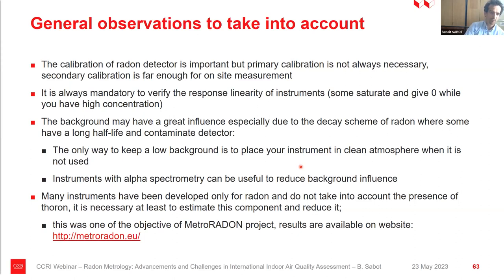But it is very important to check the linearity of instruments, because for some, you may get just a value of zero because they are totally saturated by high activity concentration. It is important to take into account the background of the detector. And often one of the problems of radon sensors is that with time they will be contaminated and you will lose detection limits. And so it's quite difficult to have very low activity concentration measurement.